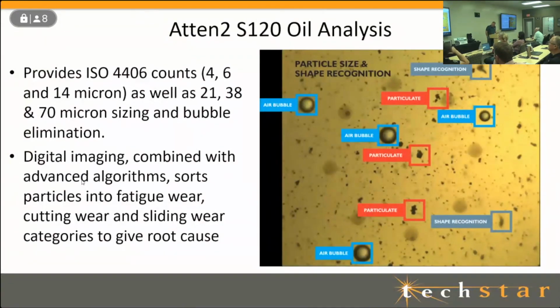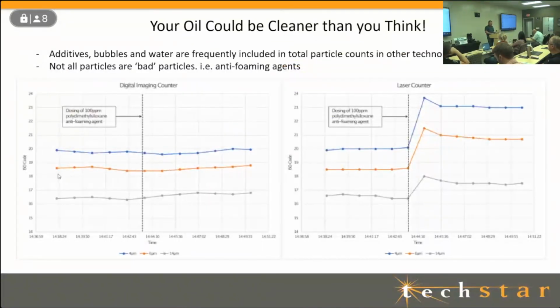And you can see here, this is an example of what the oil looks like as it's passing through the sensor and it's being analyzed. If you look off to the right there, you'll see different shapes and sizes of wear particles. You'll see some air bubbles in the mix there. And it actually pulls those air bubbles and things out of your total particle count. So it gives you a much more accurate count for your ISO. For those that don't know, there's a standard, the ISO 4406, and primarily it's looking at the 4 micron, 6 micron size. In addition, this covers 14 microns and 70 microns. So the algorithms and the database of online image files inside of this is basically doing all your analysis internally. So your output from this device via Modbus is those particle counts.